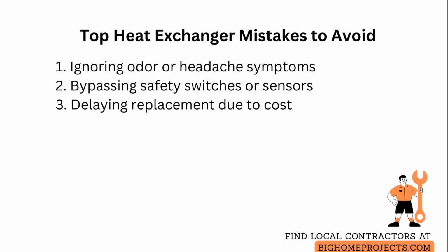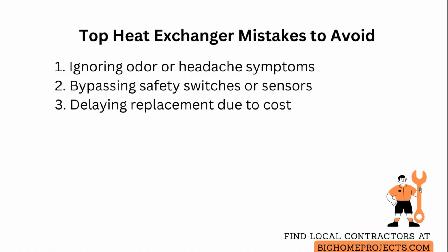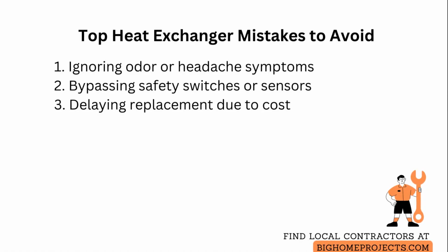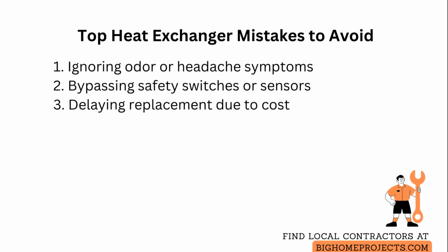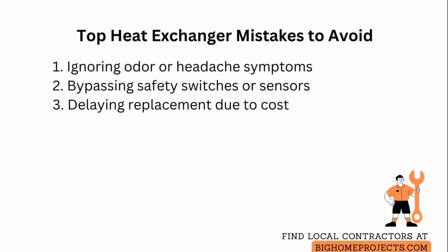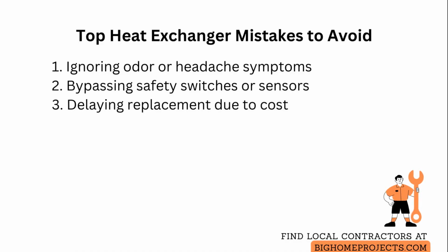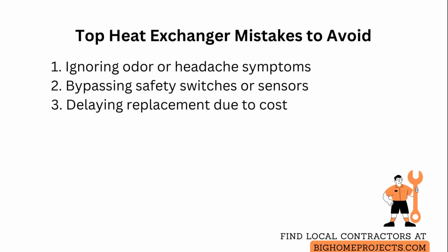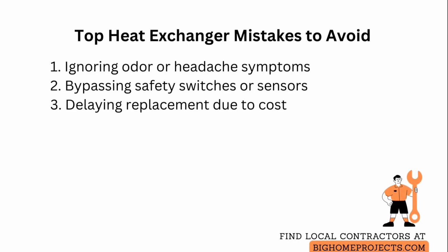Common mistakes lead to the worst outcomes, so do not ignore strange odors or intermittent headaches and attribute them to something else, because those are classic signs of carbon monoxide exposure and demand immediate action, which means leaving the home and calling emergency services if symptoms are present. Another frequent error is trying to bypass safety switches or flame sensors to keep heating working, and that is dangerous, so do not override controls. Have a technician diagnose and replace faulty components.